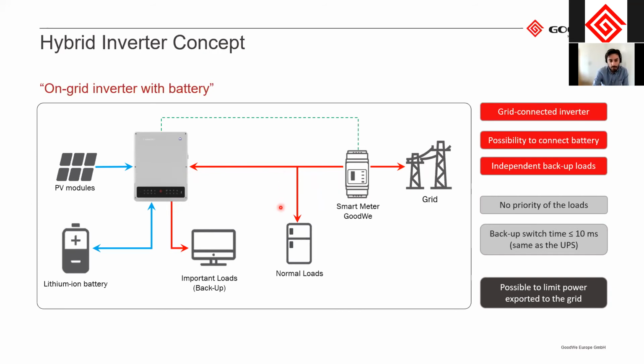And when the grid is on, internally at the circuit board they're all treated as the same output, so to say. So even the backup loads can be supplied in case you don't have any PV and no battery. The backup loads can still be supplied by grid electricity. So they're not an external load, so to say. The only difference between the backup loads and the normal loads is when the grid fails. So when there's a grid shortage or outage, then this one here will disconnect. Let me.